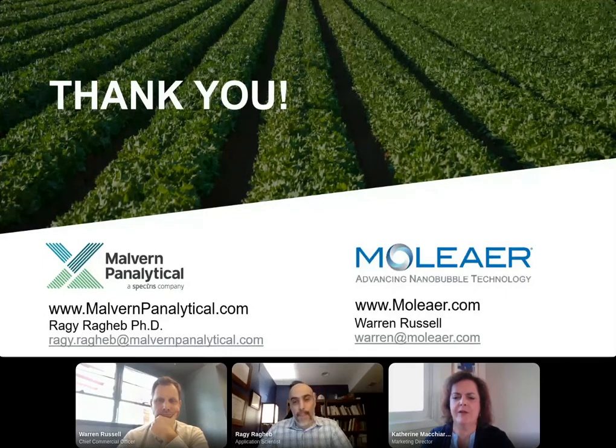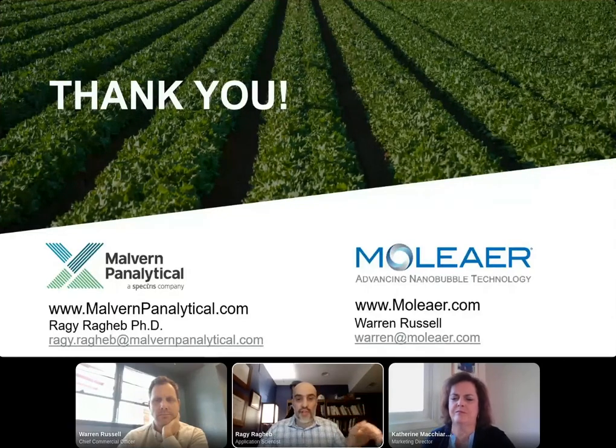Can we use zeta potential and Nanosight for a non-aqueous system? Yes, you can. There is a way to incorporate an O-ring metal top plate that handles both aqueous and organic-based solvents for Nanosight analysis. For the Zetasizer, you can use not only our polystyrene-based cuvettes for aqueous-based measurements, but also our glass or quartz cuvettes for organic solvent-based measurements.